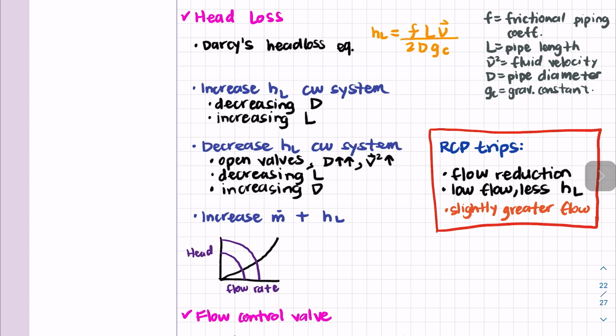And the magnitude of this head loss due to friction is going to depend on the fluid velocity, the roughness of the pipeline surface, and the length and diameter of the pipeline. We already mentioned turbulence, change in direction, and obstruction of the path can also cause head loss, right? And that can also result in increased friction and turbulence, as well as a reduction in the fluid's pressure or head. So it's important to know how we are affecting that. But to calculate head loss, we have Darcy's equation, and this is the equation that we are going to use, right? This equation uses the frictional piping coefficient, the pipe length, the velocity of the fluid, the pipe diameter, and the gravitational constant.